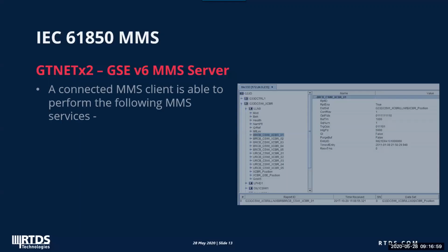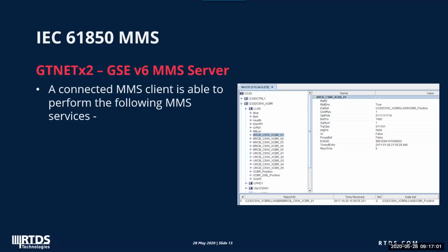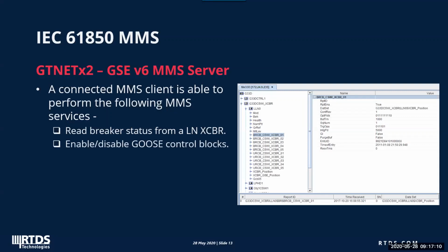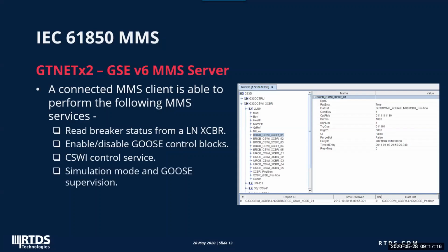Just a little more touch on the server feature. When a simulation case involving GSE version 6 is running, the GTNet X2 module acts as an IEC 61850 server. A connected client may perform some of the functions as listed here, such as reading breaker status, enabling and disabling Goose control block, sending CSWI control command to operate a breaker, and more.